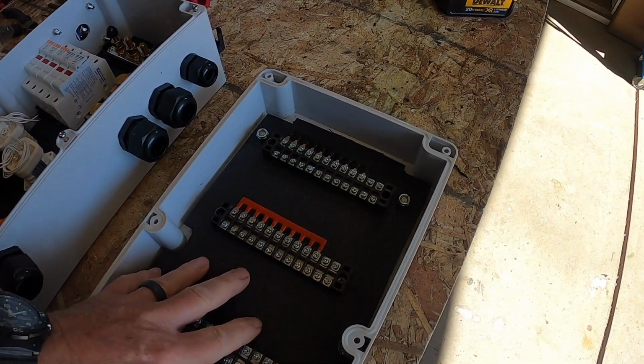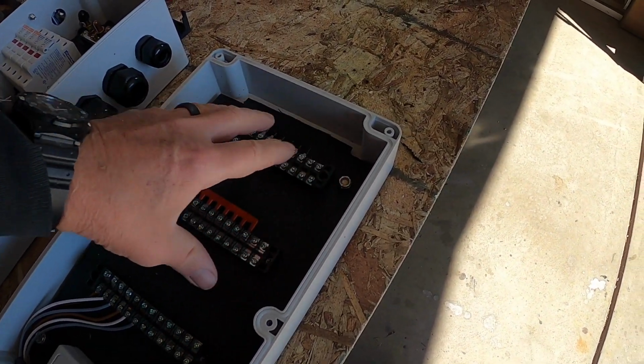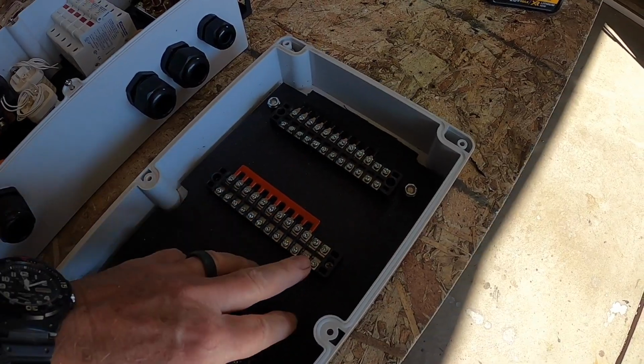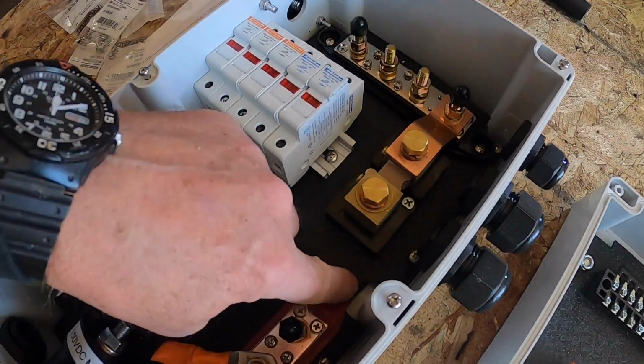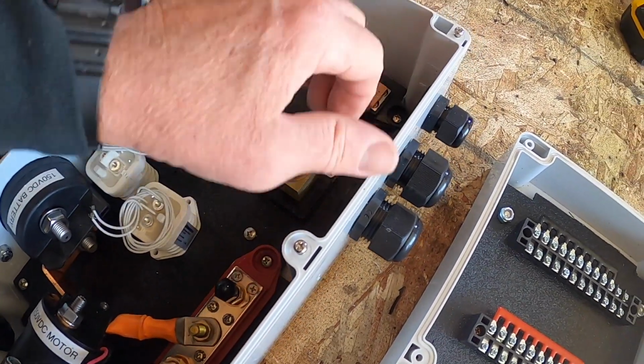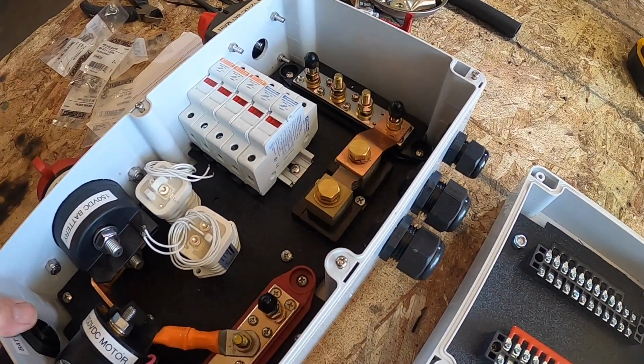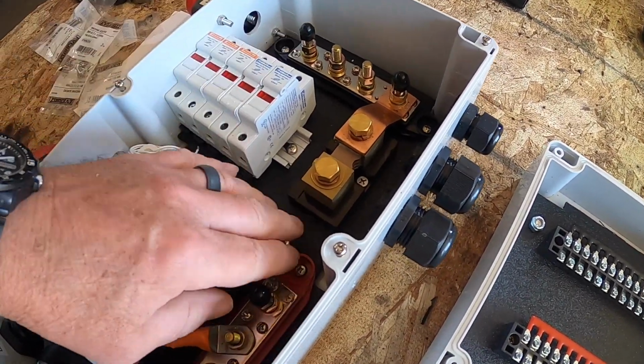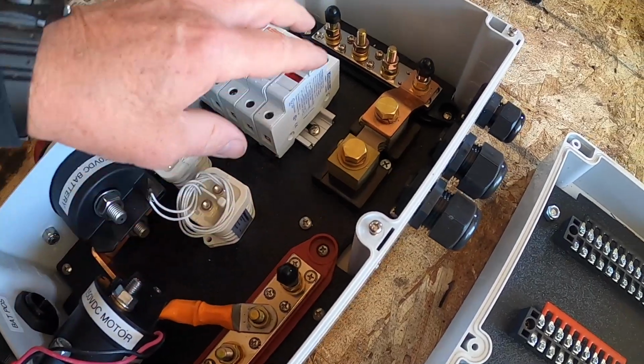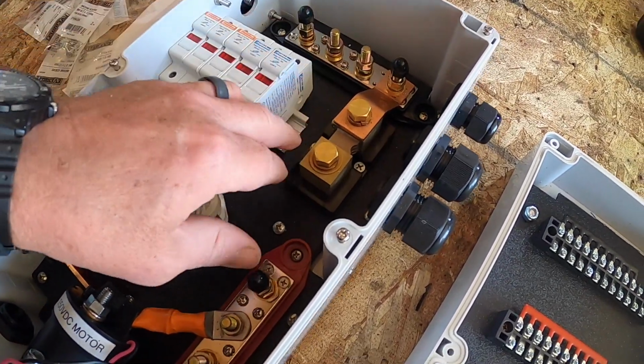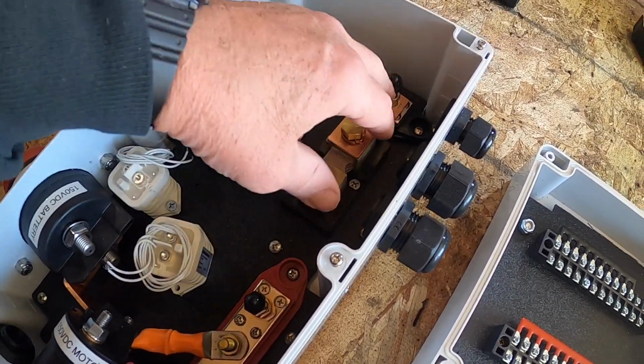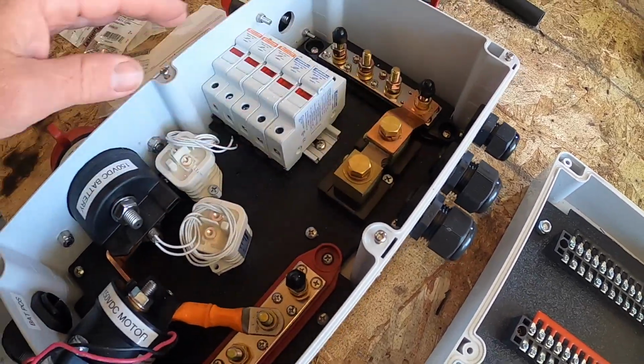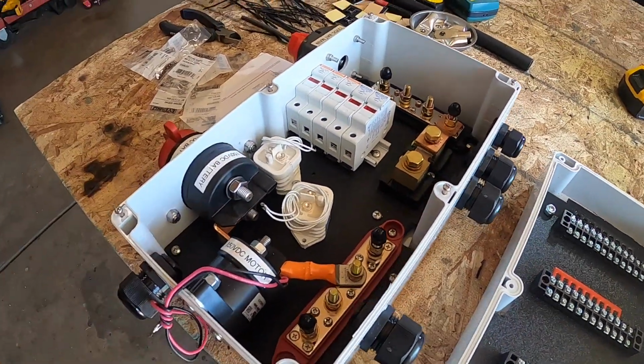Also, I had to take a piece of ABS plastic and create a standoff area so I can run the screws down for the terminals. And then also I used the existing standoffs in the electrical box here to cut a piece of ABS into the base and screw that down. That way I have clearance for running all my mounts for the bus bars, the shunt, the contactors, etc.